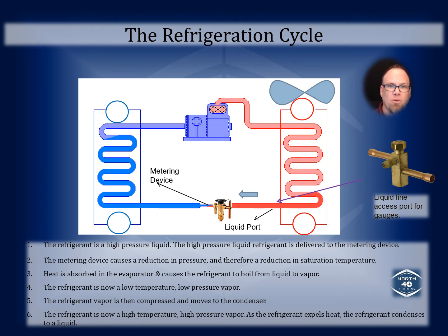If you charge in liquid form into the compressor from a tank with no throttling valve, you can hear and you can visibly see on your amp gauge that the amp draw will go up, and you can hear that noise change in the compressor as the liquid's being dumped in there, and it doesn't like what it's chewing on. And some of the more modern compressors will actually go out on overload at that point. So we need to make sure that by the time the refrigerant gets to the compressor, it's 100% vapor form.